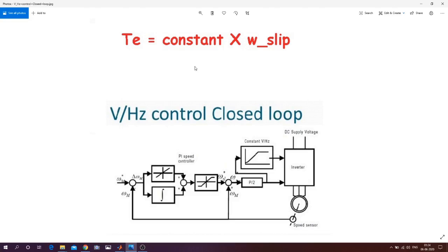Now this demanded torque is connected with omega slip with a constant. So this is one of the most important parts. When you provide a constant over here, it will give you slip. That constant has to be given by a limiter. Now you give the slip, and from here you give the measured speed, so these two add up to provide you the synchronous speed.